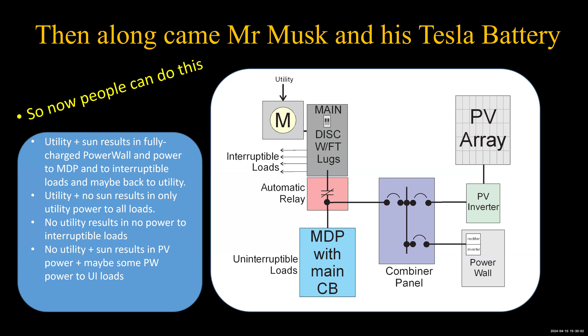So anyway, here's the results: yes utility and no sun—you still have utility power going everywhere. But if the utility goes down, then you don't have power to the interruptible loads, but you do have power to the uninterruptible ones. And you have power until the battery runs dry or until the sun comes up. And just like that, piece of cake.